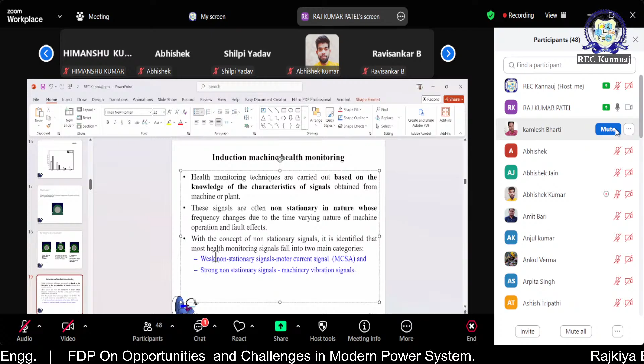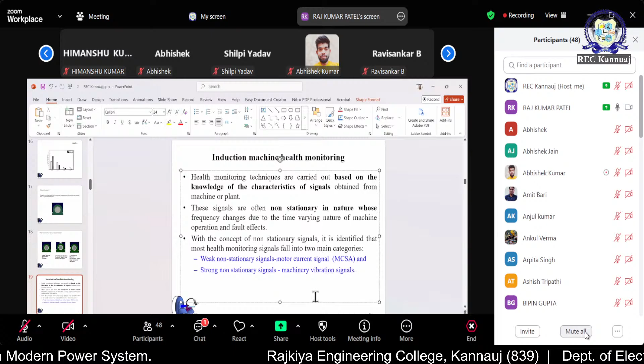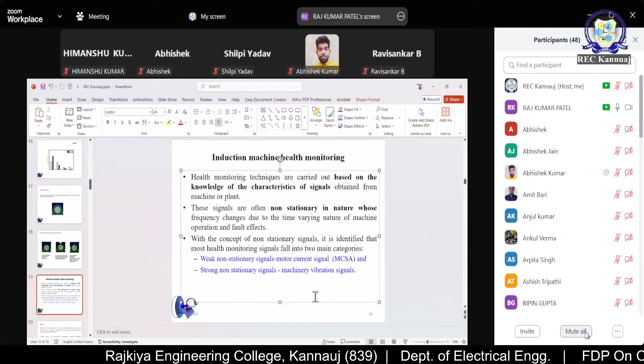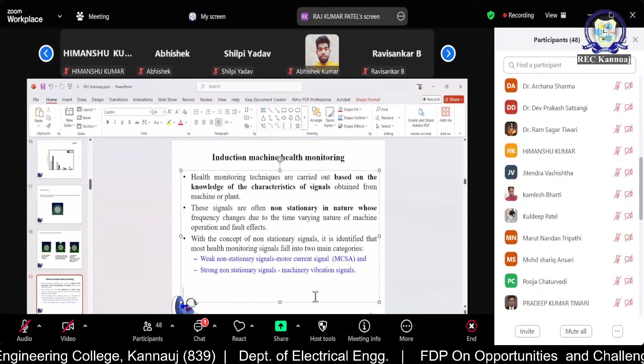There are two types of non-stationary signals we can identify in the machine: one is the current signal, and the vibration signal is a very strong non-stationary signal, while the current signal is a weak non-stationary signal. So both signals, current and vibration, are non-stationary, but vibration is strong while MCSA, the motor current signal, is basically a weak non-stationary signal.